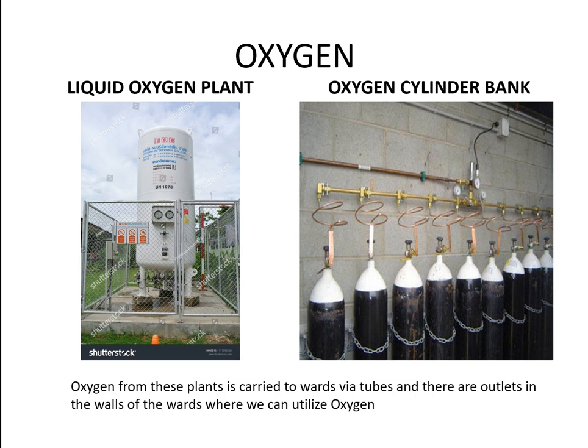So the oxygen from the liquid oxygen plant as well as the oxygen cylinder bank will be carried to the wards via tubing systems, and will be used in the ward. These are very expensive procedures. So having a liquid oxygen plant or oxygen cylinder bank is difficult. I mean, when it comes to maintenance, it's very difficult to maintain this aspect. So very few hospitals throughout our motherland have this facility.